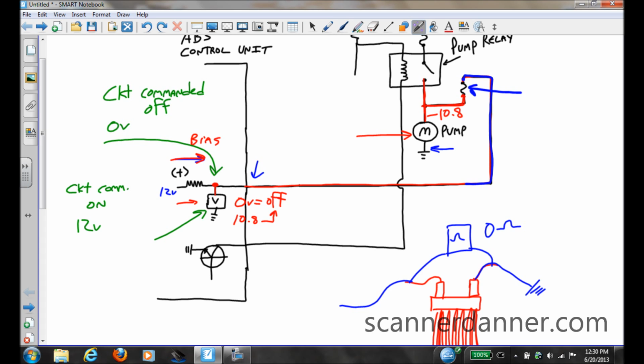So why is that fuse there? The only answer I can give you for that fuse, guys, this is a hot feed, right? It comes from the motor. What if this wire shorted to ground in here without this fuse? It would blow the pump motor fuse. So the only thing I can figure is this is there to protect this wire only.